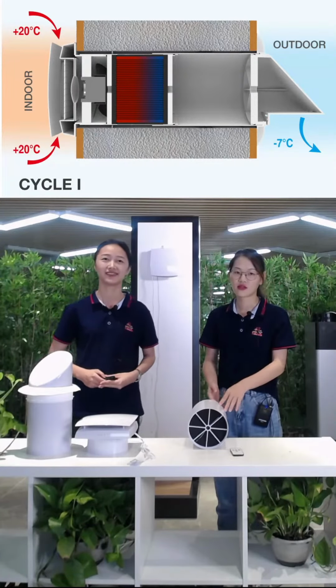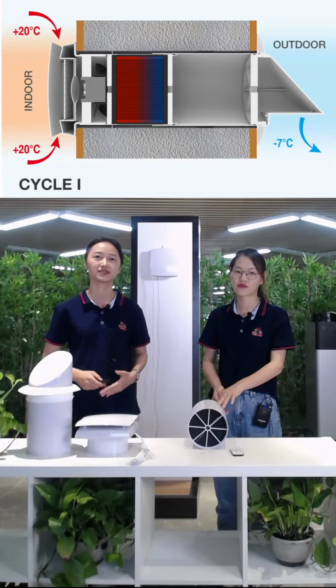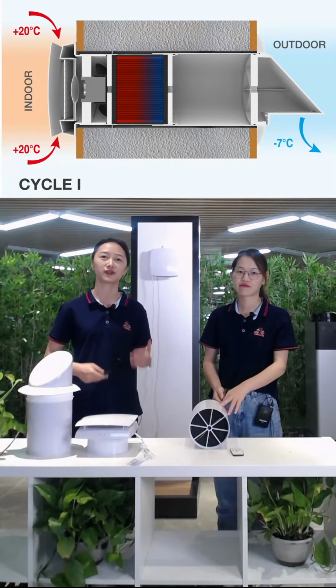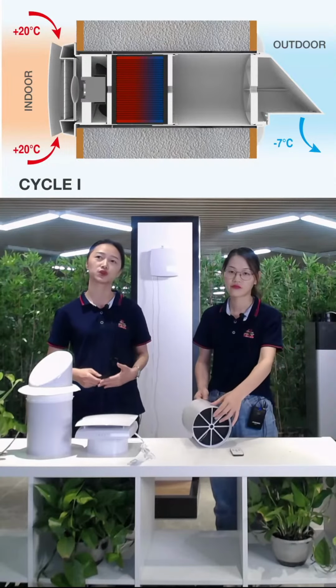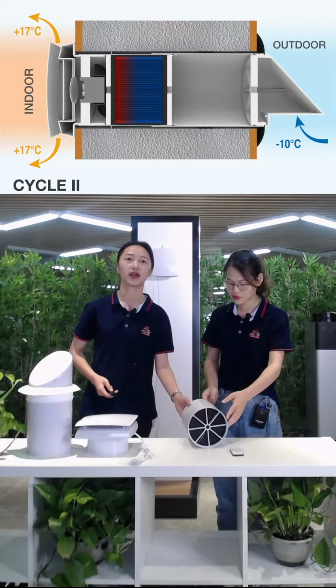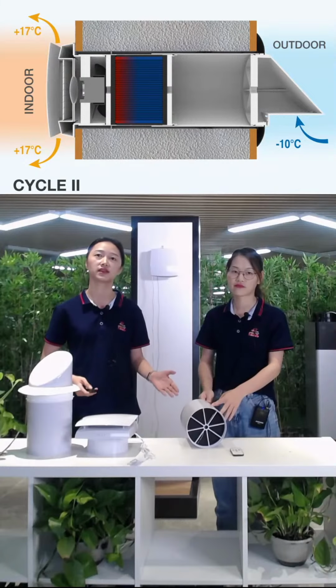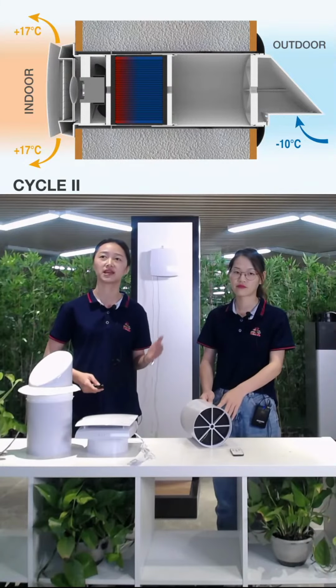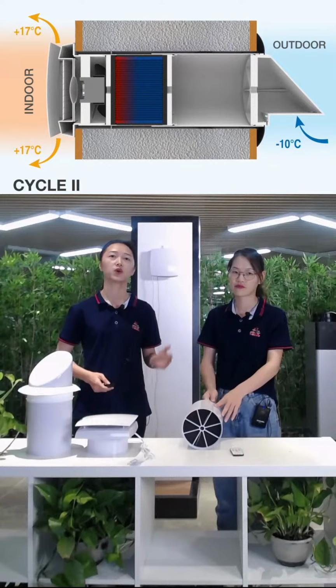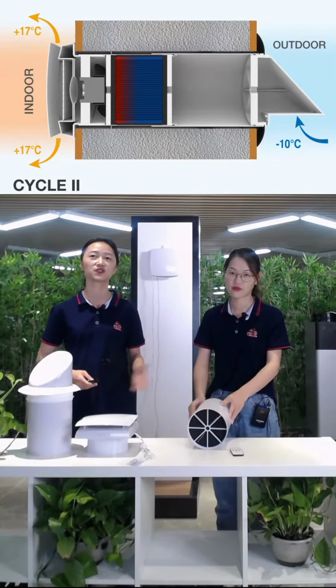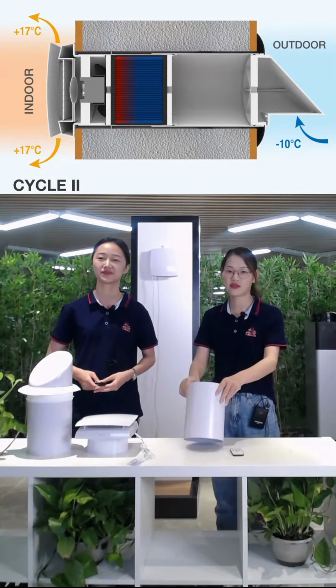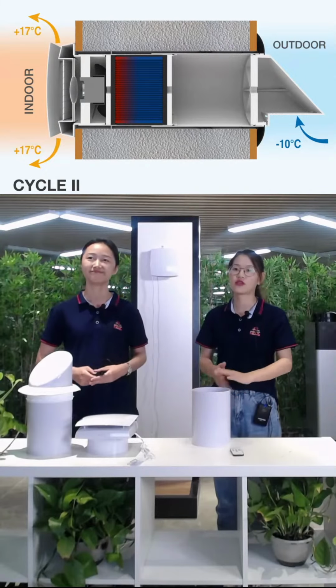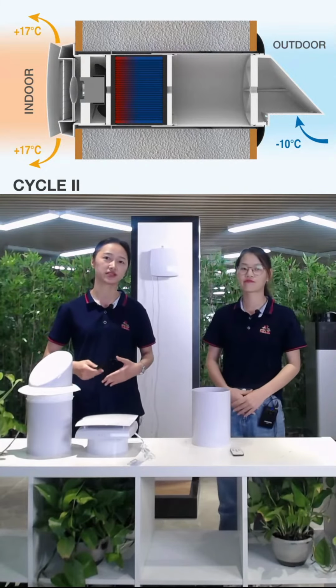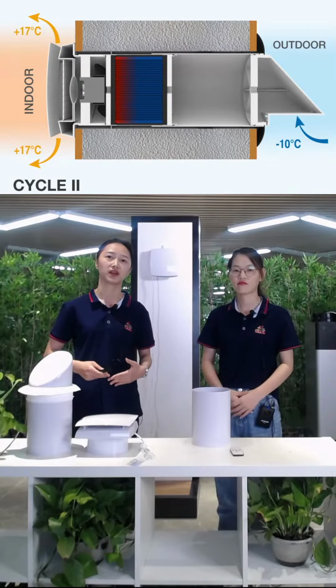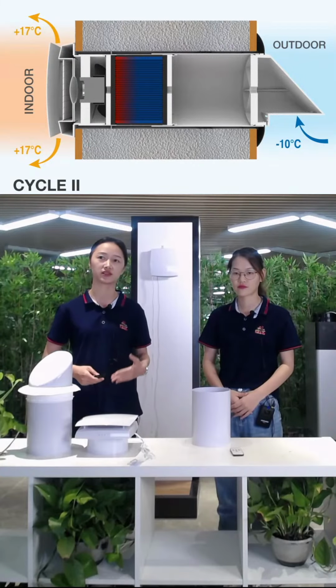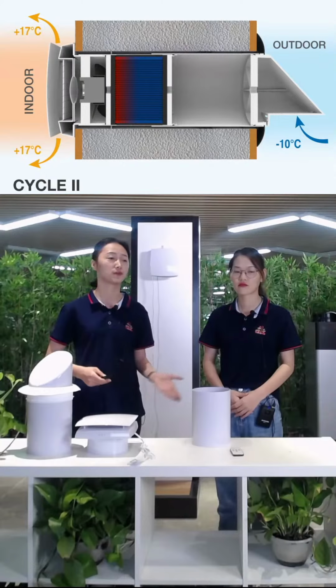Yeah, the second cycle. Then in the second cycle, the fresh but cold outdoor air flows through the heat exchanger and absorbs the accumulated heat and moisture so that the temperature of the supply airflow will be close to the room temperature, also in 65 seconds. 65 seconds for each cycle. When the energy regenerator gets cold, the ventilator switches to the air extract mode. The cycle starts from the beginning.